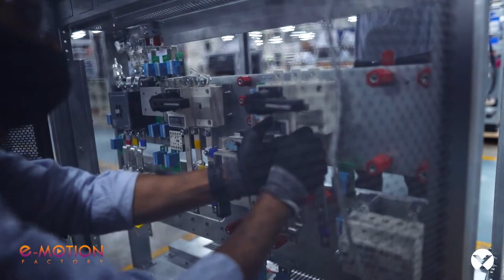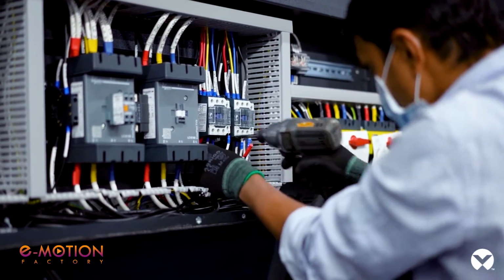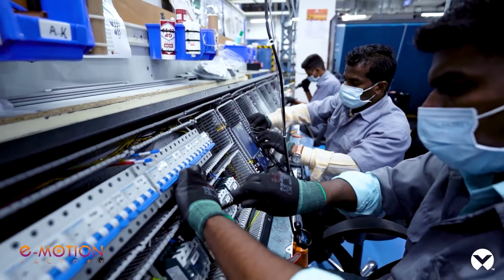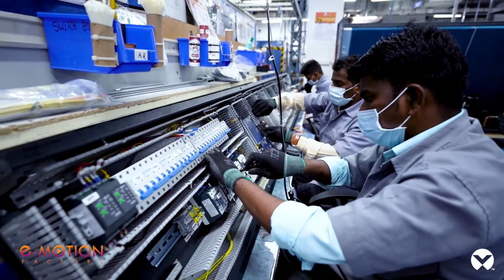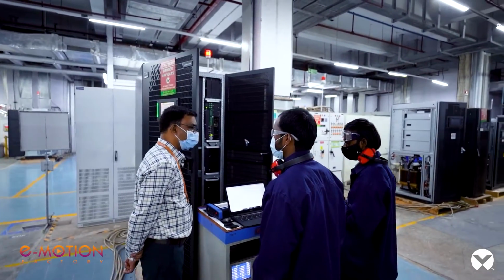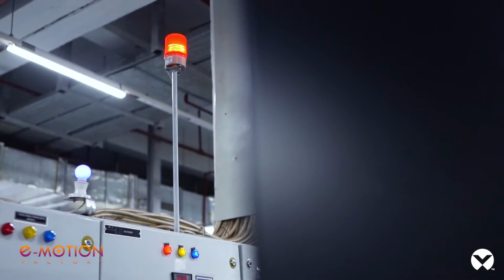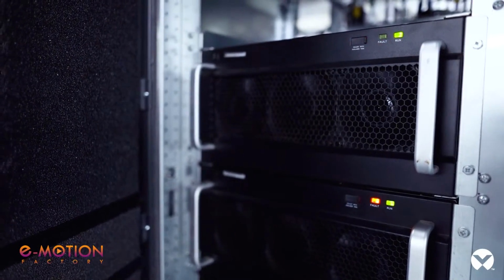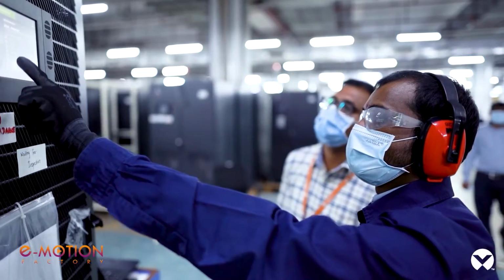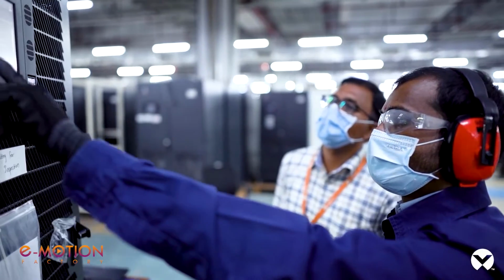We use flow lines for anything less than 200 kVA, plus dedicated flow lines to do all kinds of modules from 30 to 50 kilowatts. I think the strong point here is the customized factory acceptance test we do for all our major customers - metro, colo, manufacturing. We have the latest equipment, the latest oscilloscopes, so we can meet the requirements of the customer's factory acceptance test in the Ambernath plant.